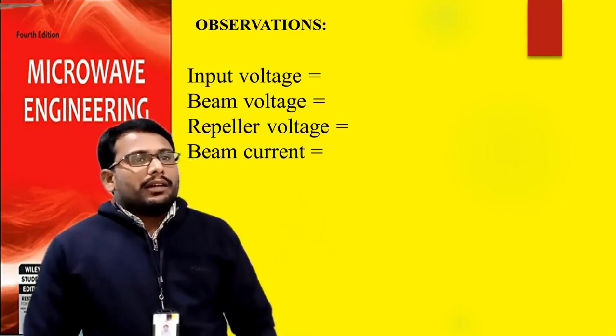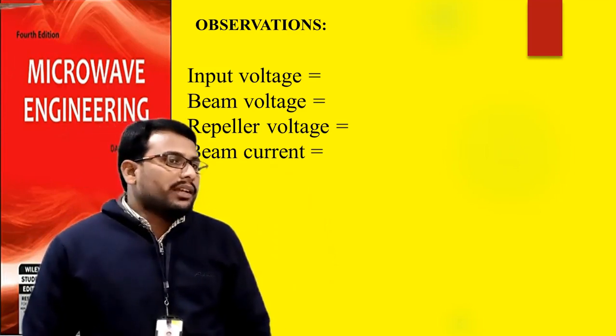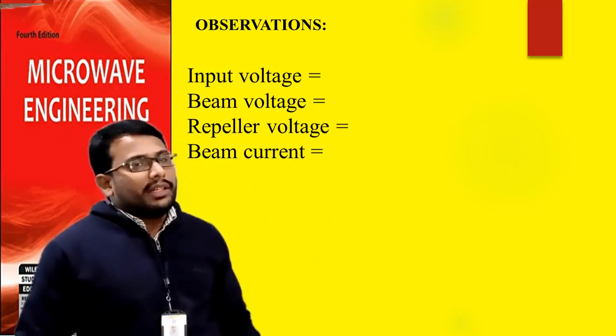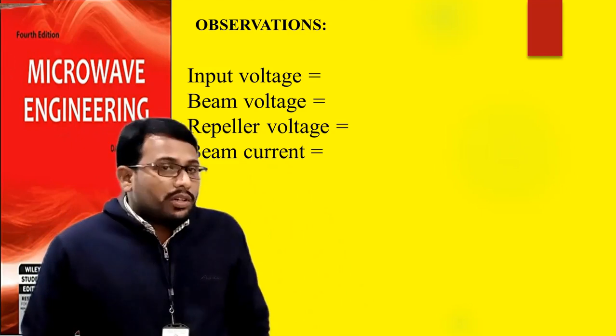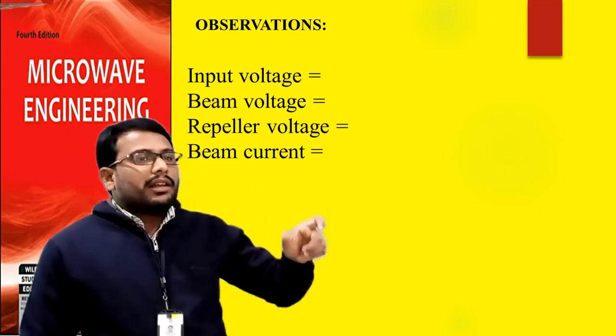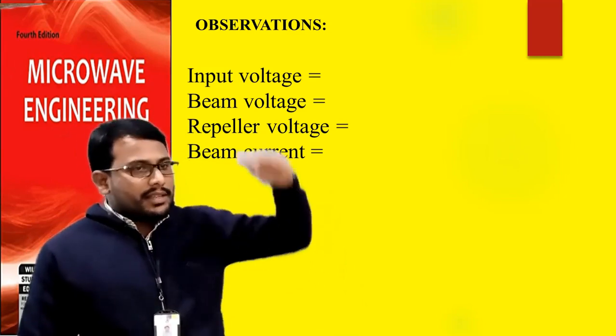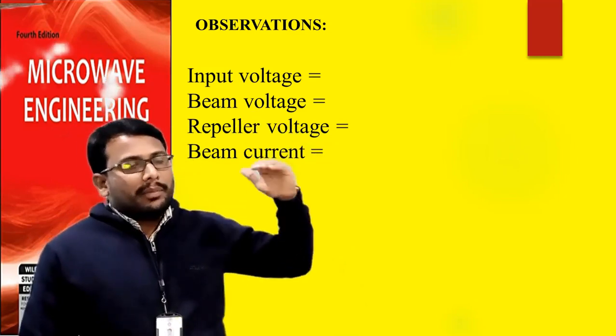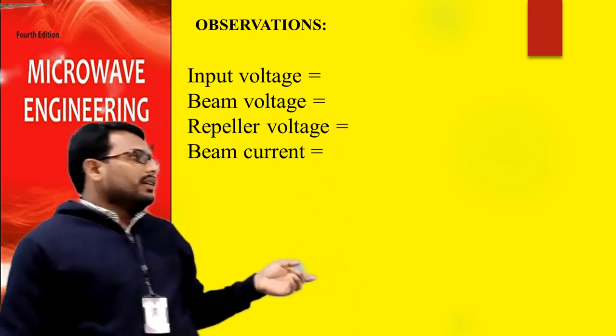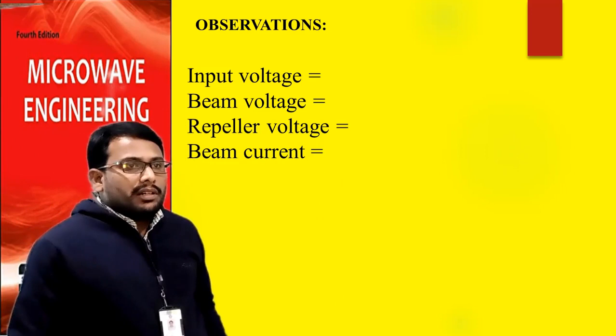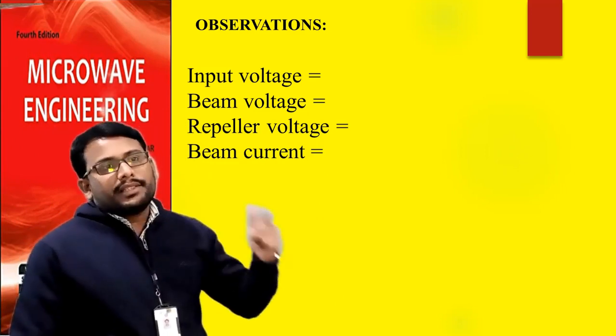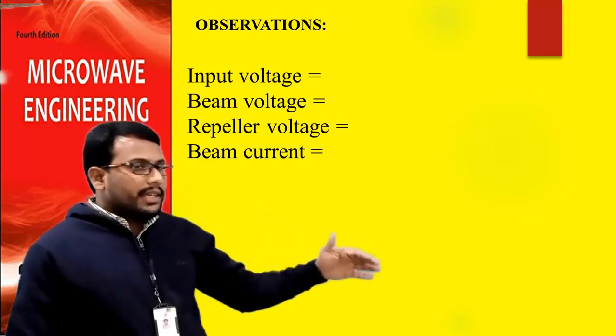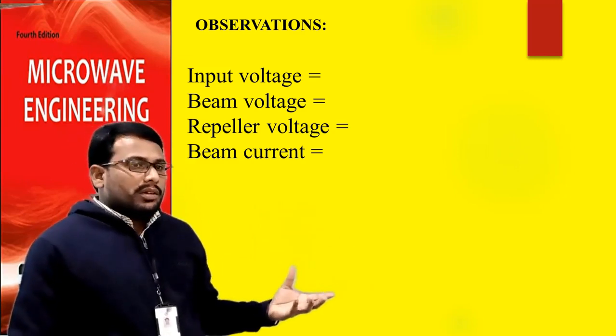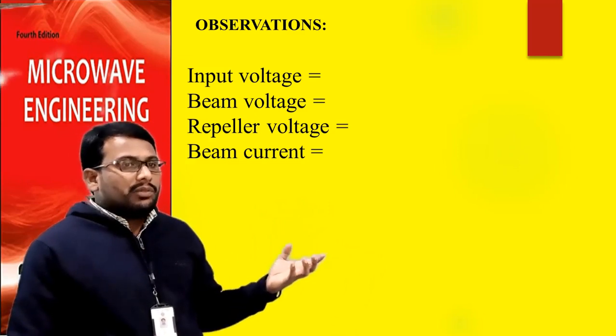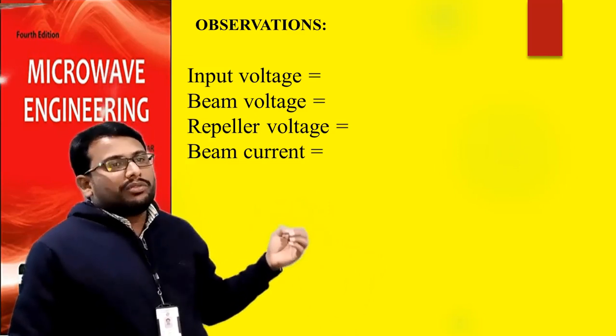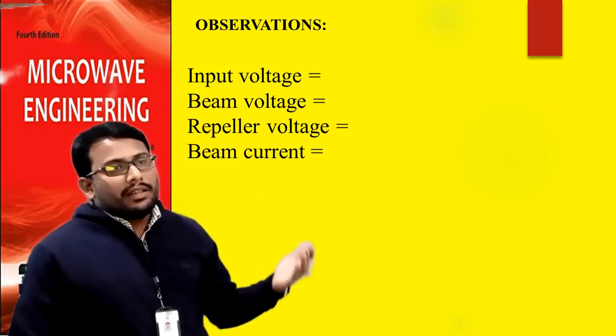Then you have to note that particular voltage as the repeller voltage, for example 201, 203. While you are rotating the knob, you see the signal strength increasing and decreasing. You have to fix the maximum signal strength. Then beam current. Beam current is always below 18 milliamps. It should not exceed 18 milliamps. If it exceeds, there is a chance of burning out. The mount operates at high powers, right? High voltages, right? So be aware, you have to fix the beam current below 18 milliamps.